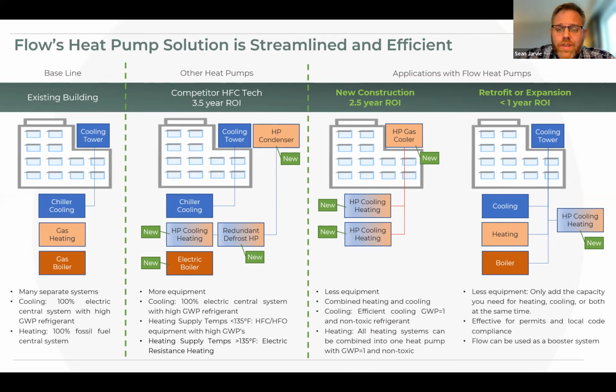So looking at that with a system like I showed everyone here earlier, there is now a heat pump that can operate cooling and heating at the same time, if it's planned that way, and can take roughly 50% of the overall footprint. And we've seen this with multiple studies that we've done in the last year. Sometimes it's as much as a 50% reduction in overall footprint. It's competitive on pricing, if not a little bit cheaper, by about 10 to 12% in some cases. And it really fits the bill, especially with a split system to hide it all over a campus or a building, especially when you're doing retrofits.